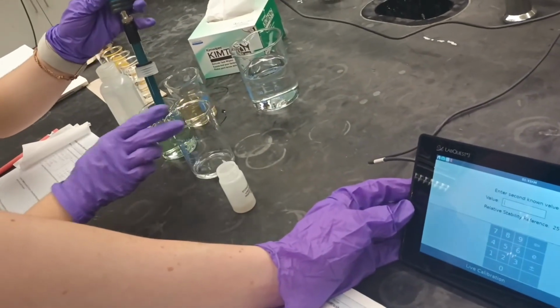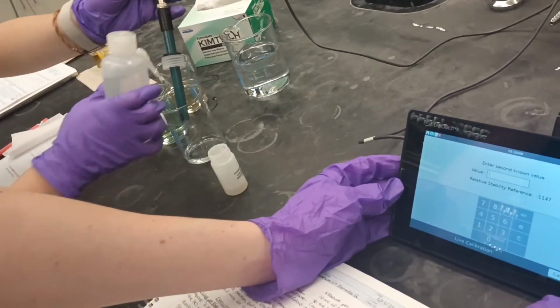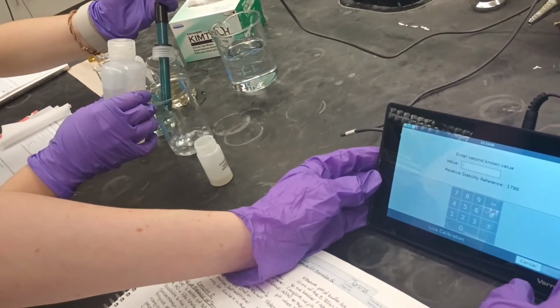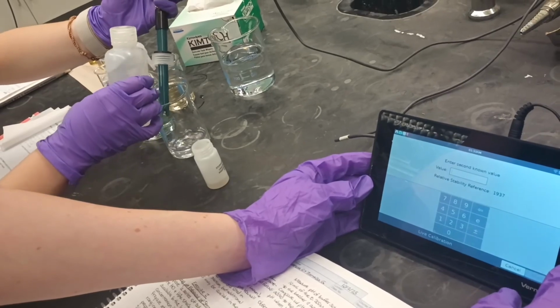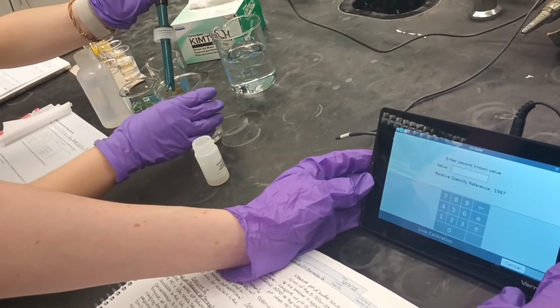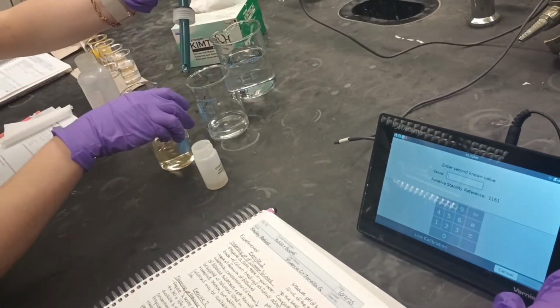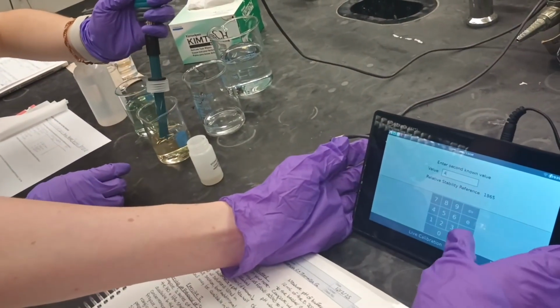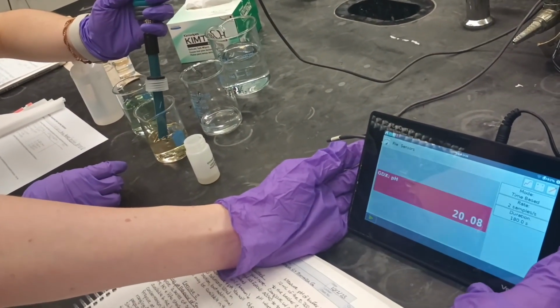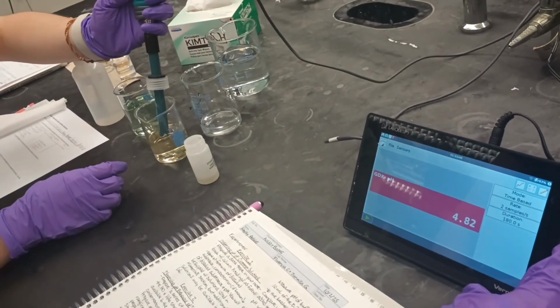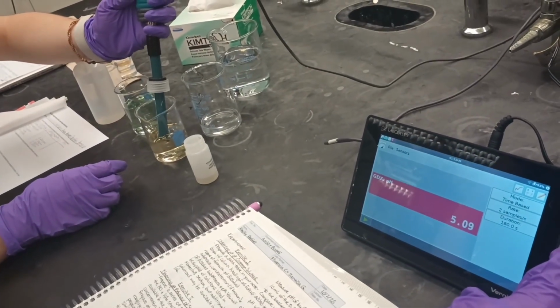First, take the electrode out of the storage solution and rinse with distilled water. Then, put the electrode in the 7 pH buffer, stir, and set the pH meter to 7. After that, rinse the electrode with distilled water again. Put the electrode in the 4 pH buffer if testing acids or 10 pH buffer if testing the bases, stir, and set the pH meter to the according pH. Then, the meter is ready to use.